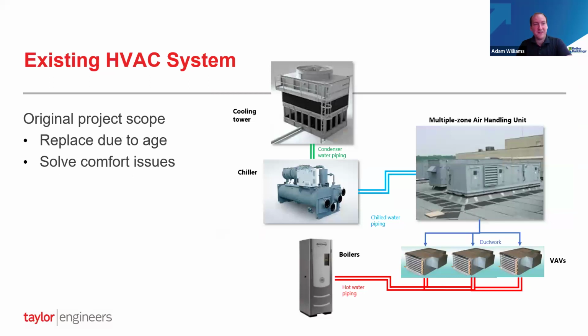So the existing system is a water-cooled chilled water plant which serves one built-up multiple zone VAV air handling unit, which then serves many VAV reheat terminal units. So those terminal units have a damper that can modulate the amount of cooled air to meet the cooling loads. And then they've got hot water piping to a hot water reheat coil with a hot water valve that can be modulated to heat up the air to meet the heating loads.